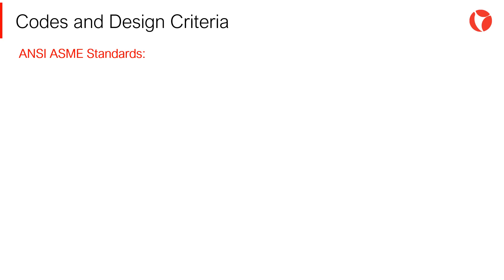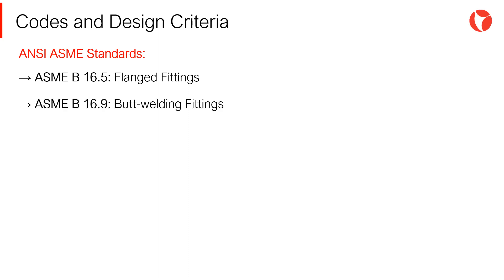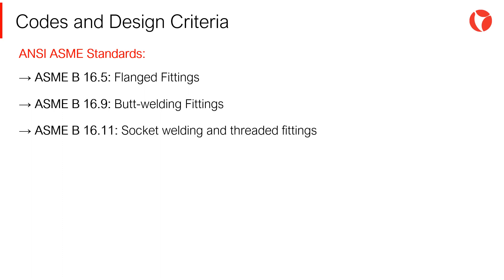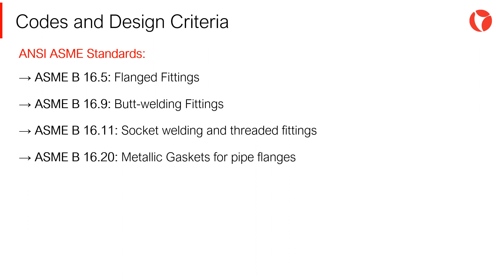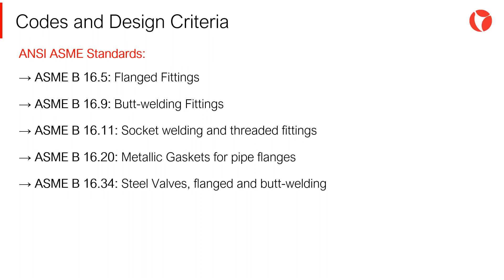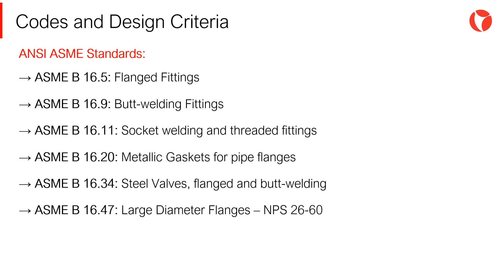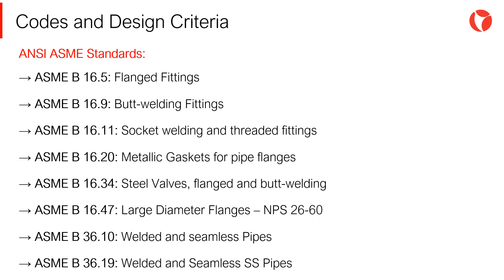The ASME standards most used in the design of piping systems are: B16-5 flanged fittings; B16-9 butt welding fittings; B16-11 socket welding and threaded fittings; B16-20 metallic gaskets for pipe flanges; B16-34 steel valves; B16-47 large diameter flanges; B36-10 welded and seamless pipes in carbon steel; and B36-19 welded and seamless pipes in stainless steel.